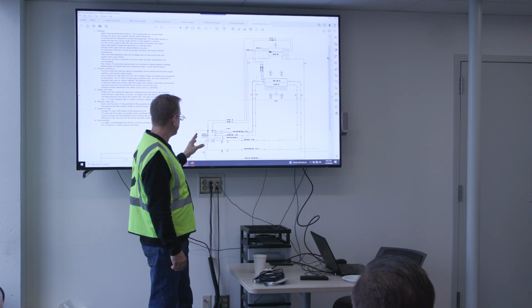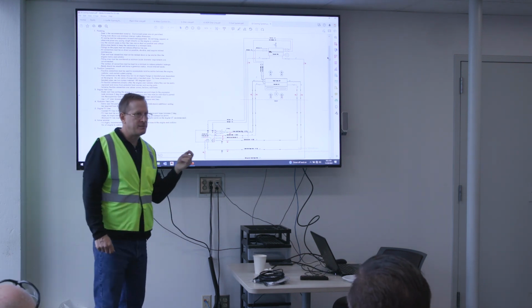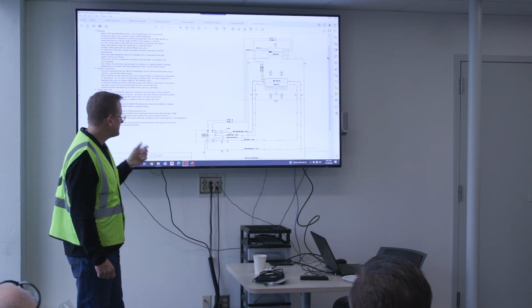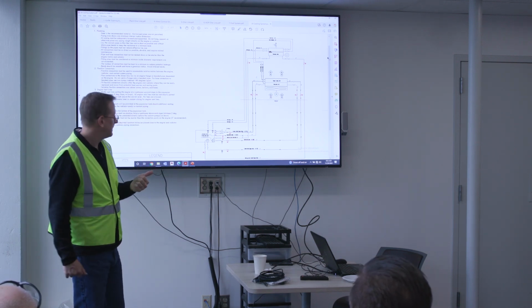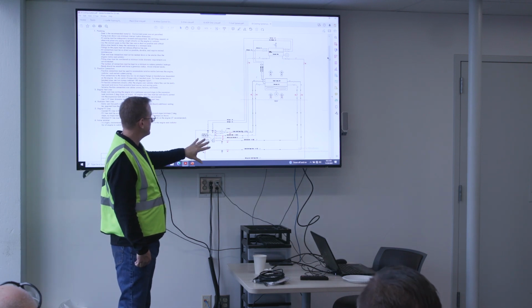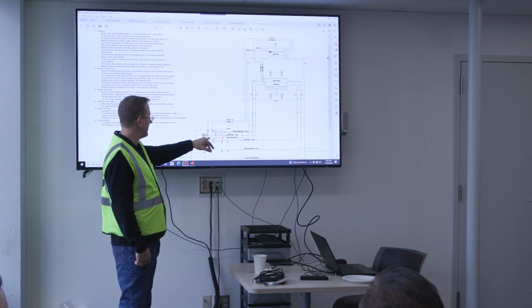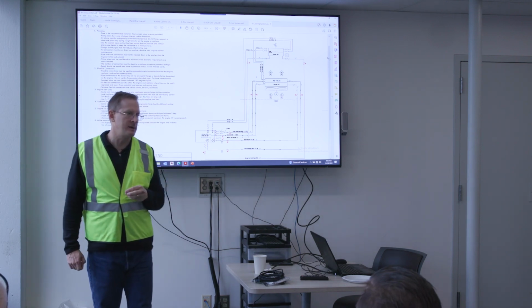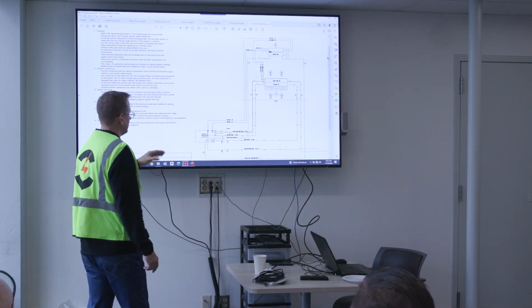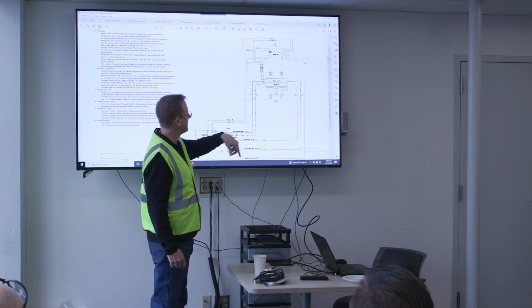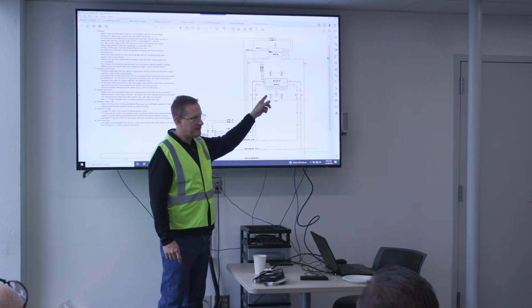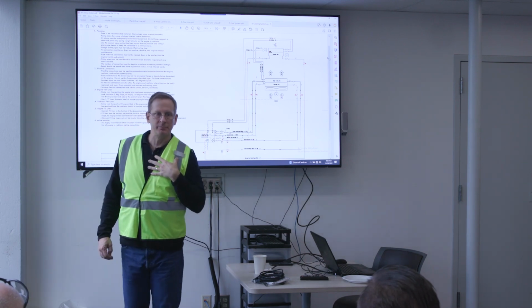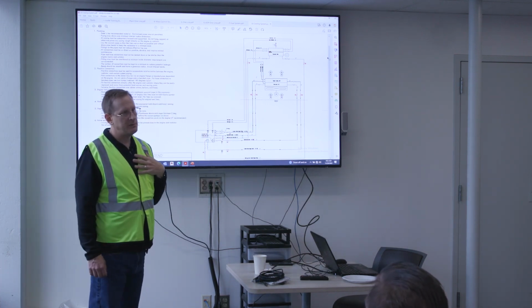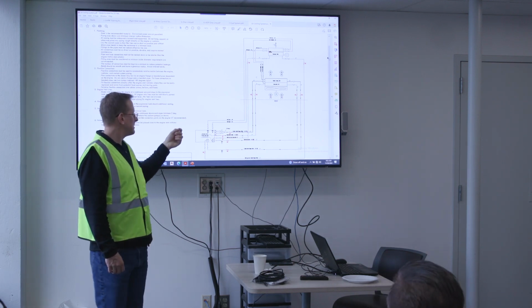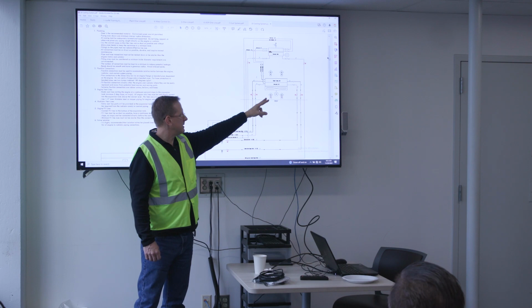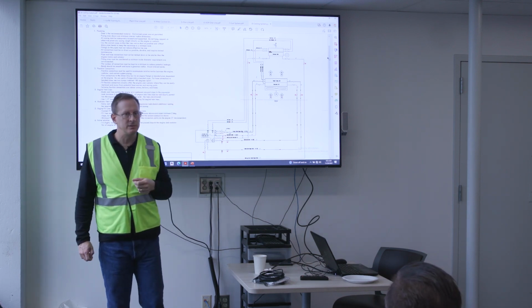So while the engine is running, there's a constant flow of cooling to the radiator for both circuits. The flow, of course, is driven by the water pumps on the engine itself. So the water pumps for the coolant on the engine will drive the water up into the radiators and back. Radiator has a fan motor, which is controlled by the Hitec PLC. So again, when the radiator is running, we give a command for the motor to engage the radiator fan so that it can cool the engine.